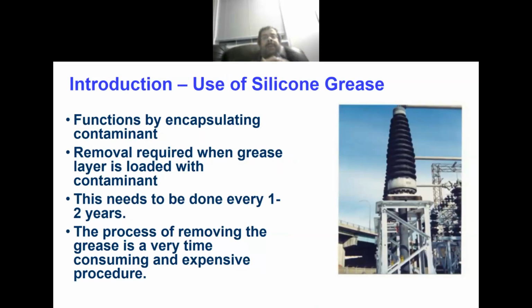Then people came up with another solution: using a sort of grease to cover the ceramic insulators, using certain materials. The last one they use is silicone grease. The silicone grease will encapsulate the pollutant and prevent the flashover, which is a perfect thing. However, people started to realize that you need to replace the material after 1 or 2 years.